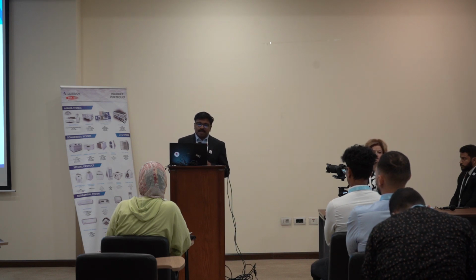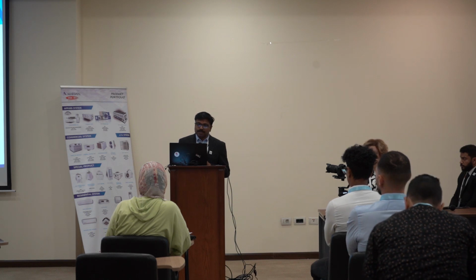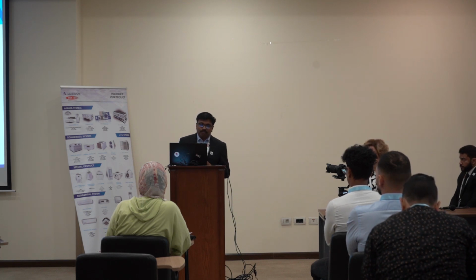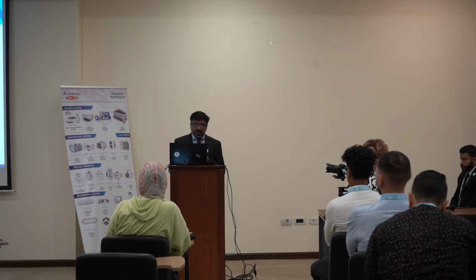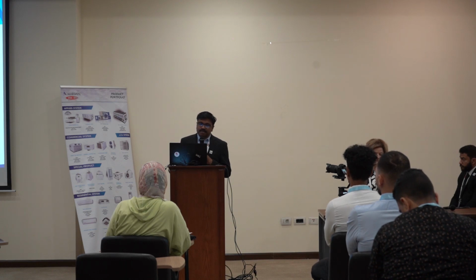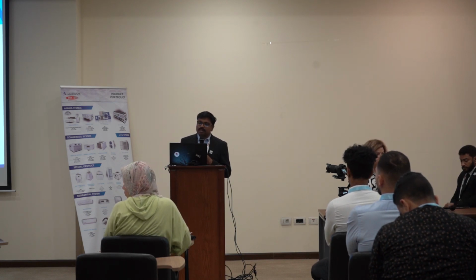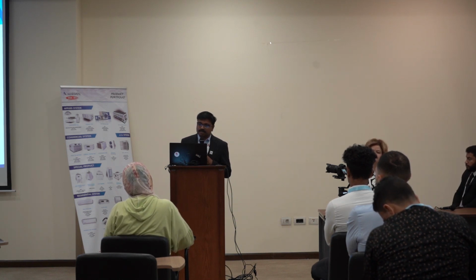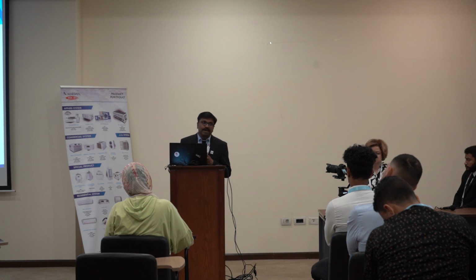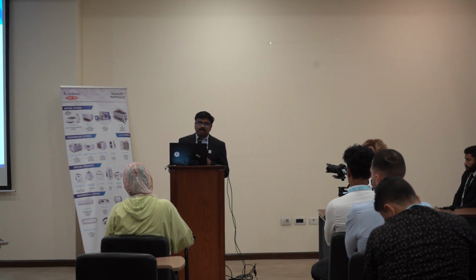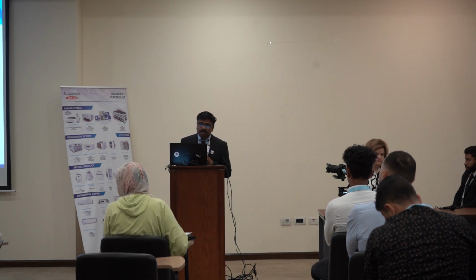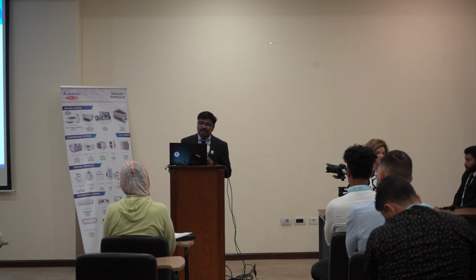And we have 13 sizes starting from 8 up to 32. So 8, 10, 12 HP in one kit, 14 and 16 in another kit, 18 and 20 in the third kit, 22 HP in one kit, 24, then 26, 28 and 30, 32. This is the last kit, the dual compressor with the dual fan combination. So there are 13 single modules, and when we combine, the maximum can be 96 HP, which is equal to 78 tons. The main feature is that it can work up to 55 degree ambient in cooling, and in heat mode it will work between minus 30 degree and plus 30 degree. So this shows a wider operating range.